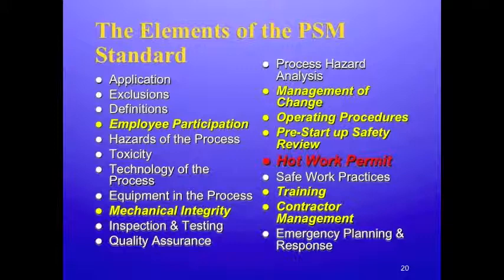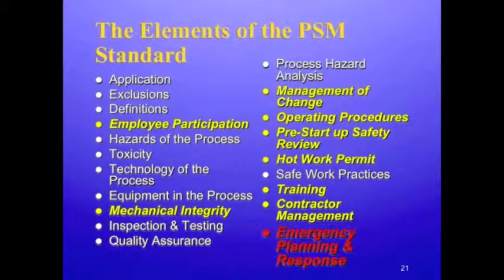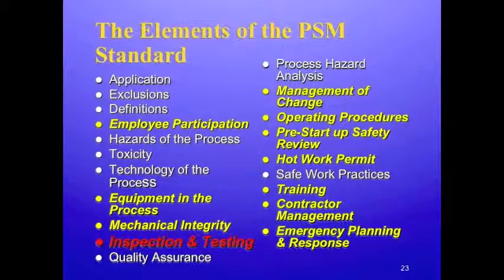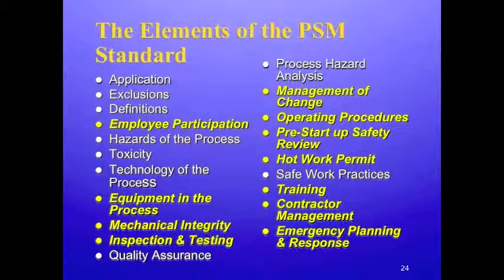The employer must review the response plan, covered under emergency planning, to ensure that procedures are adequate for the installation hazards. Although management of change provisions cover interim changes, after the new valve is in place, the process safety information will have to be updated before process hazard analysis is updated or revalidated to account for the potential hazards associated with the new chemical. Also, inspection and maintenance procedures and training will need to be updated, covered under mechanical integrity. In summary, 11 PSM elements can be affected by changing one valve. A reviewer, inspector, auditor, or compliance officer would check a representative number of these 11 elements to confirm that the required follow-up activities have been implemented for the new valve.